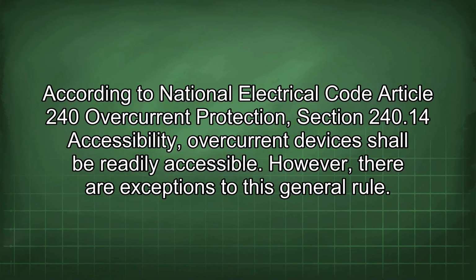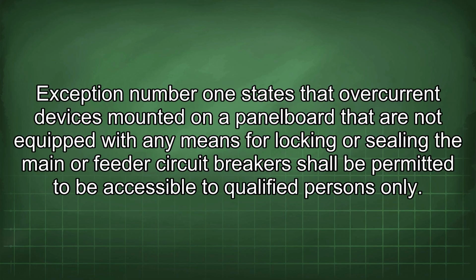According to National Electrical Code Article 240 Overcurrent Protection, Section 240.14, accessibility: overcurrent devices shall be readily accessible. However, there are exceptions to this general rule. Exception number 1 states that overcurrent devices mounted on a panel board that are not equipped with any means for locking or sealing the main or feeder circuit breakers shall be permitted to be accessible to qualified persons only.